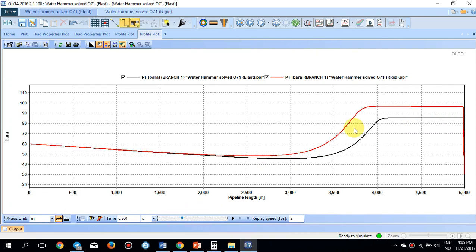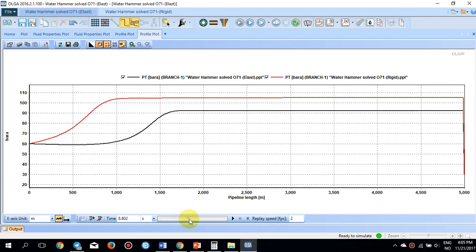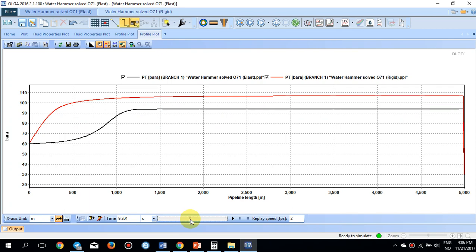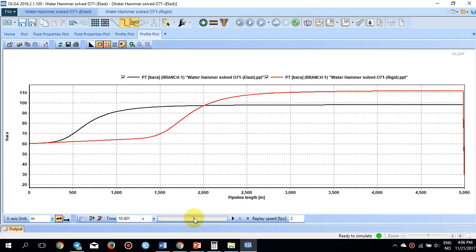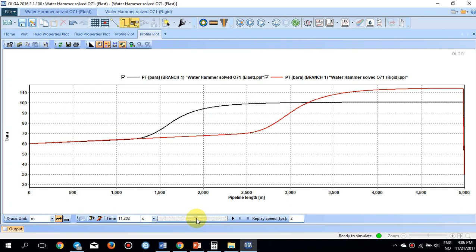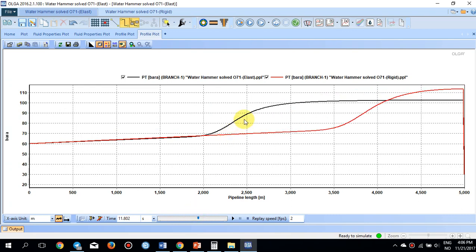There is also a phase difference between the two pressure waves: the elastic case travels slightly slower while the rigid case propagates faster downstream. This same pattern is visible all the way along the pipe. The elastic wall gives some space to accommodate the pressure wave, significantly reducing the peak compared to the completely rigid wall case.